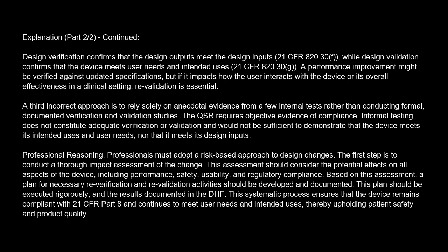Professional reasoning. Professionals must adopt a risk-based approach to design changes. The first step is to conduct a thorough impact assessment of the change. This assessment should consider the potential effects on all aspects of the device, including performance, safety, usability, and regulatory compliance. Based on this assessment, a plan for necessary re-verification and revalidation activities should be developed and documented. This plan should be executed rigorously and the results documented in the DHF. This systematic process ensures that the device remains compliant with 21 CFR Part 820 and continues to meet user needs and intended uses, thereby upholding patient safety and product quality.